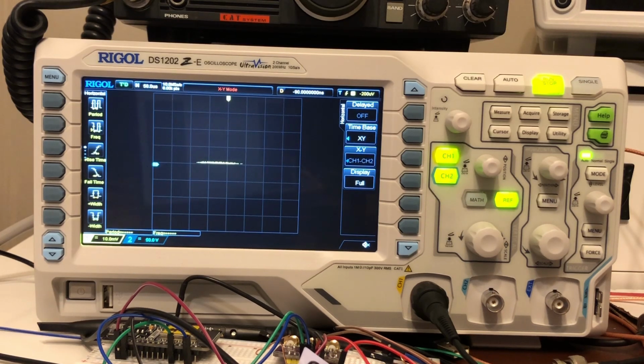The following functions are not available in XY mode: delayed sweep, vectors, protocol decoding, acquisition mode, pass-fail test, waveform record, and to set the persistence time. Method 2, use the shortcut measurement function. Refer to the phase 1-2 and phase 2-1 measurement functions of delay and phase on page 6-27.